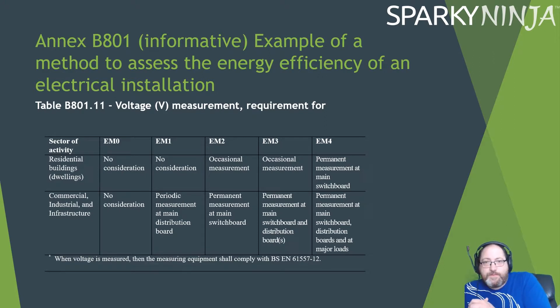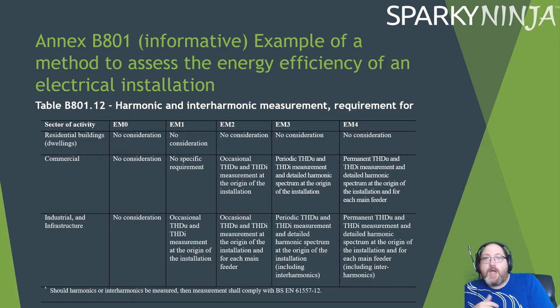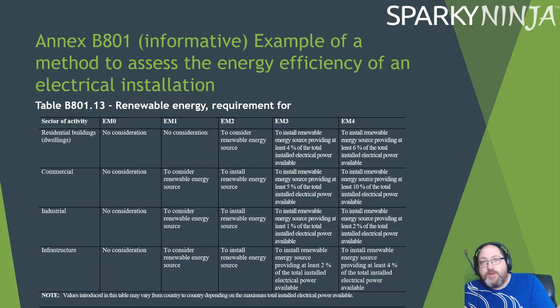Voltage measurement: permanent measurement at the main switchboard scores lower; permanent measurement at the main switchboard, distribution boards, and major loads scores higher. Harmonic and interharmonic measurement is also included as a category. For renewable energy sources: installing a renewable energy source providing at least 6% of total installed electrical power scores well — the thresholds are 10% for commercial and 2% for industrial, which makes sense as industrial is far more demanding.